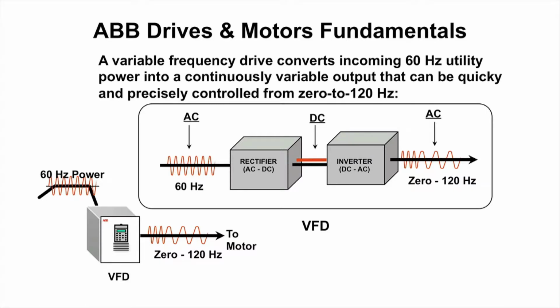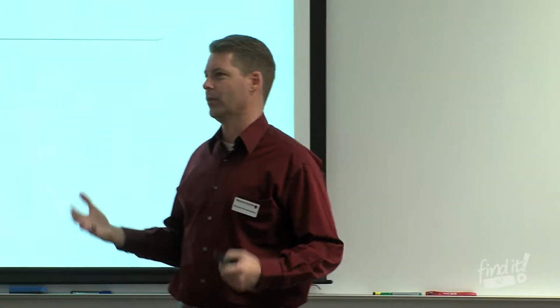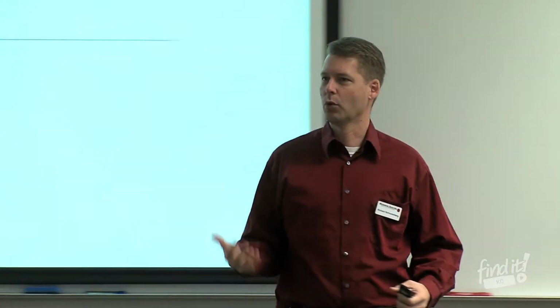Any frequency we want can come out of the VFD. The VFDs today go up to 600 hertz. Not that most of the fans and the pumps are ready to do that, but the VFD has more capabilities for speed than the equipment that we're driving.